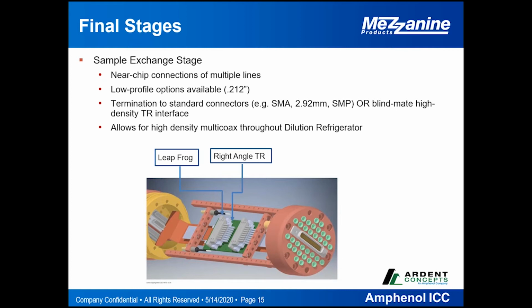This is a good example of a sample exchange which gets loaded in. It's a quick sample exchange, so you don't have to bring the dilution refrigerator back up to room temperature. In this case, you have a near-chip solution, so the chip lives on a PCB within the sample exchanger. We have our TR right angles and leapfrog connectors that touch down on the PCB footprint directly next to the chip, so you're getting very close to the device under test.